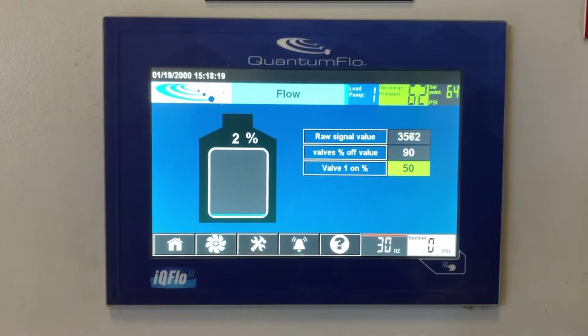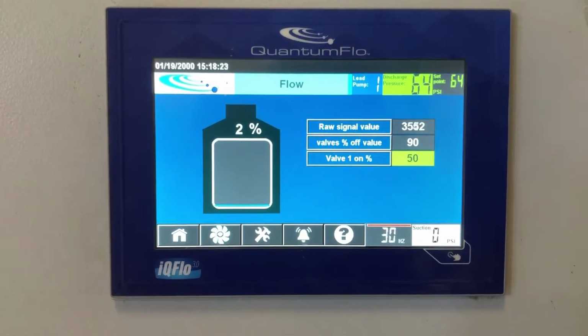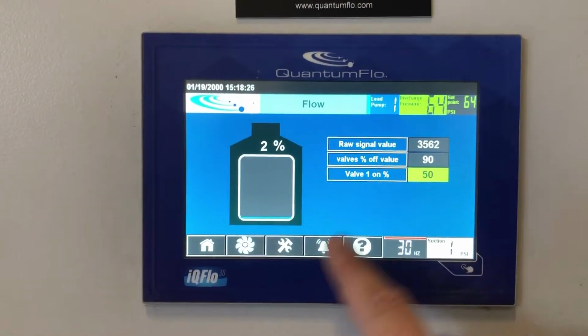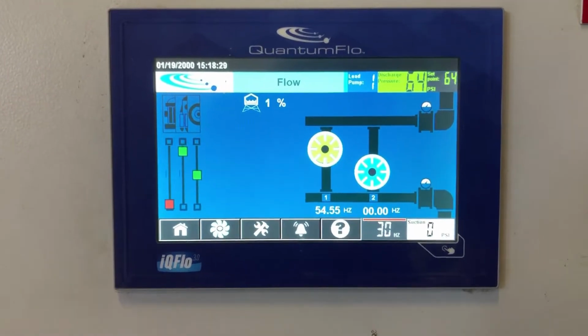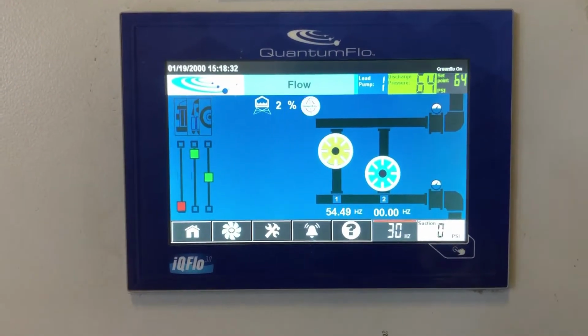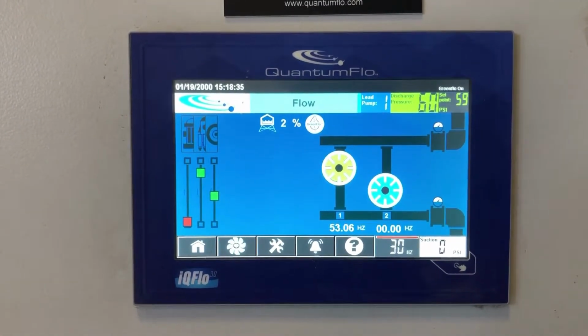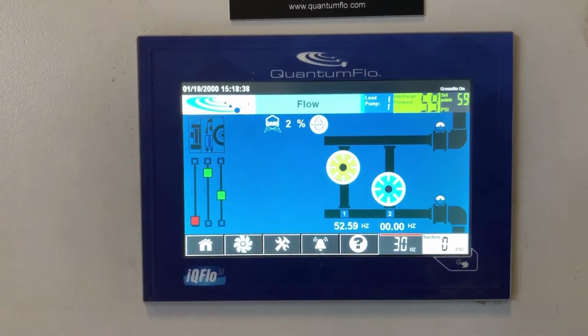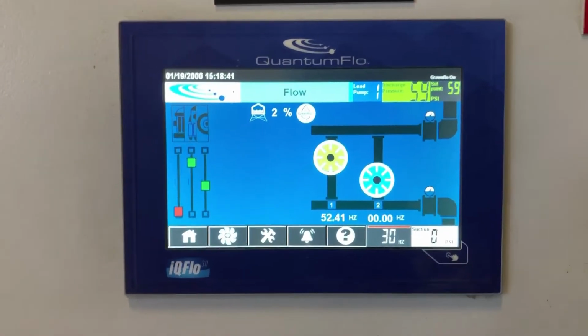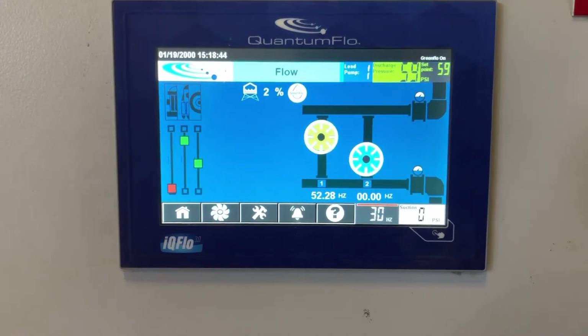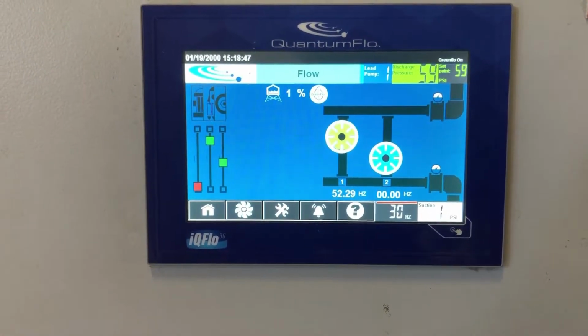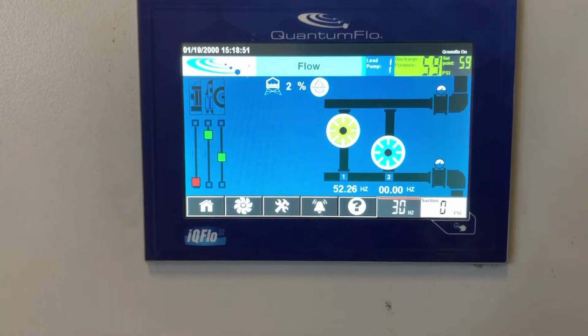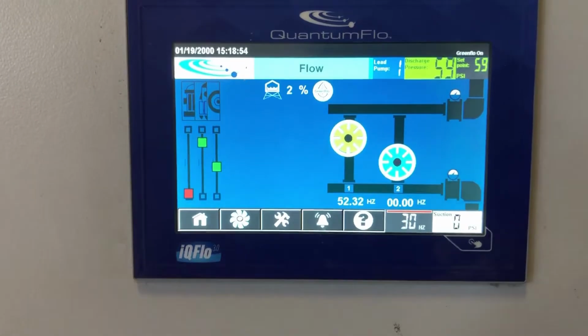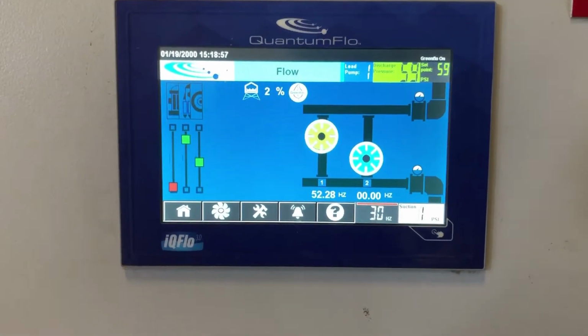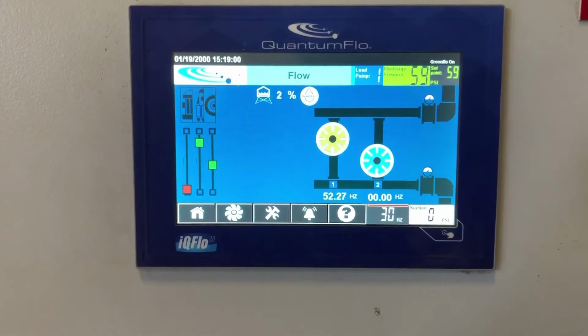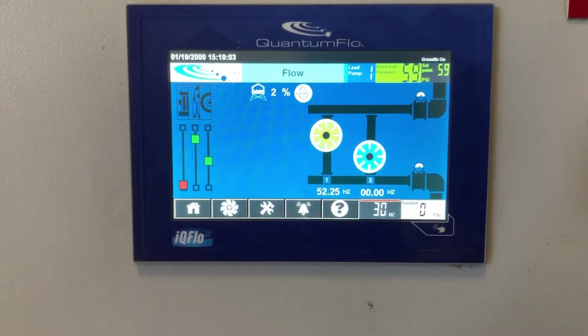We do have an actuated valve to bring in the reuse water for this one. So it's detecting flow occasionally. This has not been connected to the irrigation system yet, so I'm not sure where any water is going, and I'm not going to leave this on for long, just in case there's a leak. We've got a level switch in each day tank for each pump system that is actually controlling the pump on and off. When that float goes down, then it shuts off the pumps.